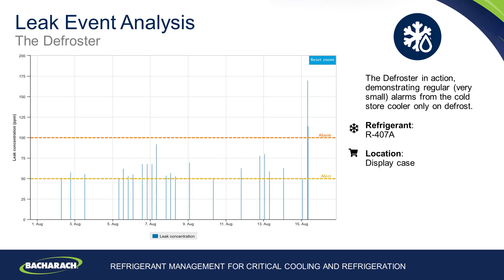Here is another example of a defrost leak in a walk-in cooler or refrigerated display case on the sales floor. Again, you can see a pattern in the leak — a regularity with the PPM values just breaching the lowest level of 50 PPM. Outside this period the leak may not be detected by the engineer, so being able to visualise the leak over a period of time aids the engineer in rectifying the leak on site.